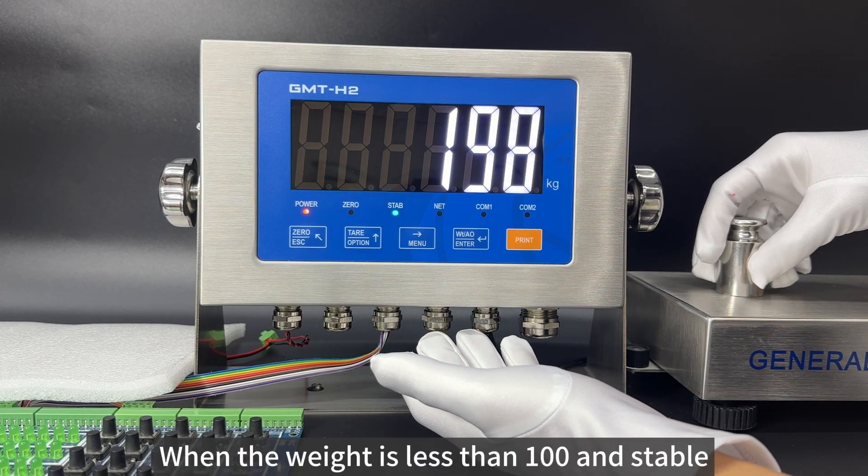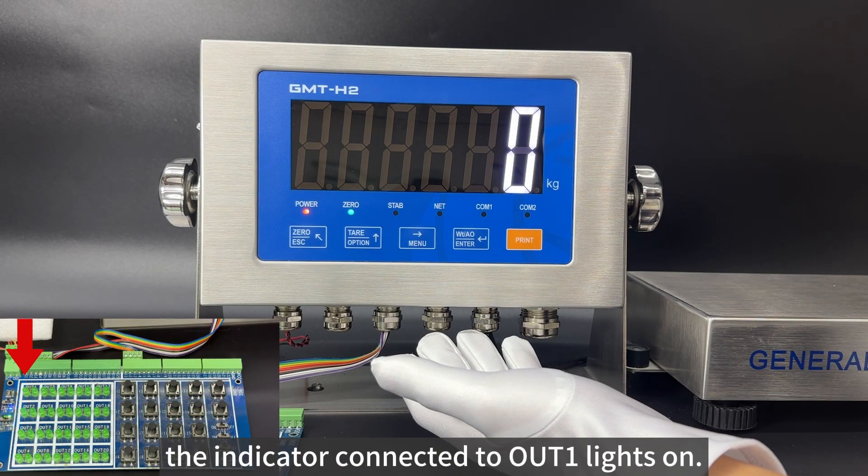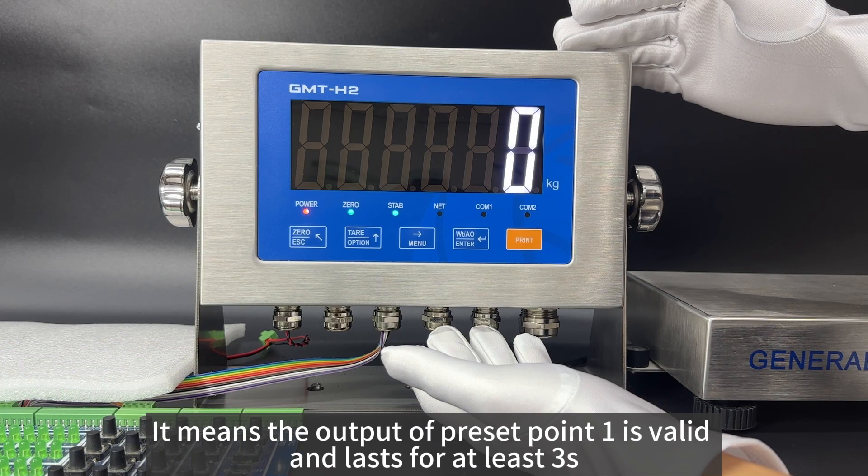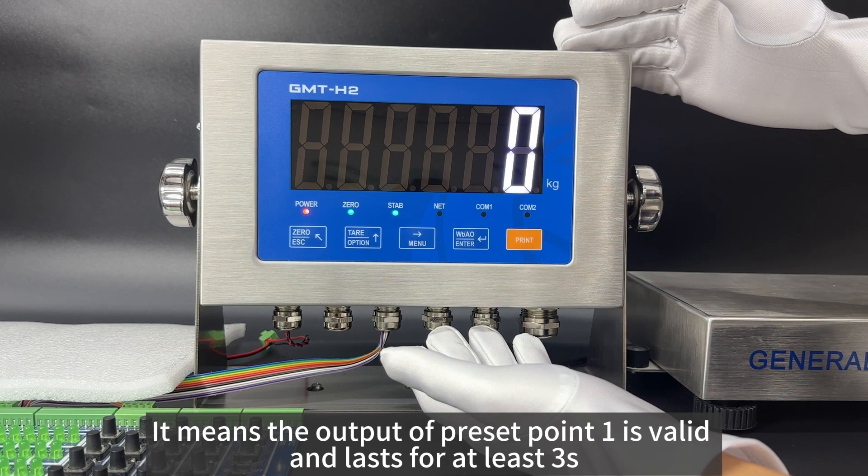When the weight is less than 100 and stable, the indicator connected to OUT1 lights on. It means the output of preset point 1 is valid and lasts for at least 3 seconds.